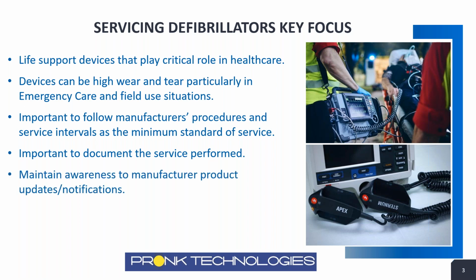It's important to also be aware of manufacturer notifications. These could be done by direct notifications to users. Manufacturers post these things on their website. The FDA has a website. They also post these things. And so it's important to keep our ear to the ground, so to speak, and be aware of anything that has come through that can impact the performance of the device that needs to be updated. Could be a software update, could be a field notification, something needs to be updated or replaced. So it's important we're aware of these things.